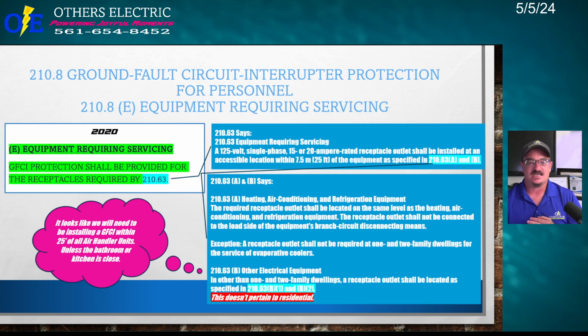Okay? So what they're saying is, if you need to put a receptacle in based on 210.63, it has to be GFCI protection. So what does 210.63 say? 210.63 says equipment requiring servicing. A 125 volt single phase 15 or 20 amp rated receptacle outlet shall be installed at an accessible location within 25 foot of the equipment specified in 210.63A and B. Okay, so what they're saying is you need a GFCI outlet within 25 foot of this equipment.